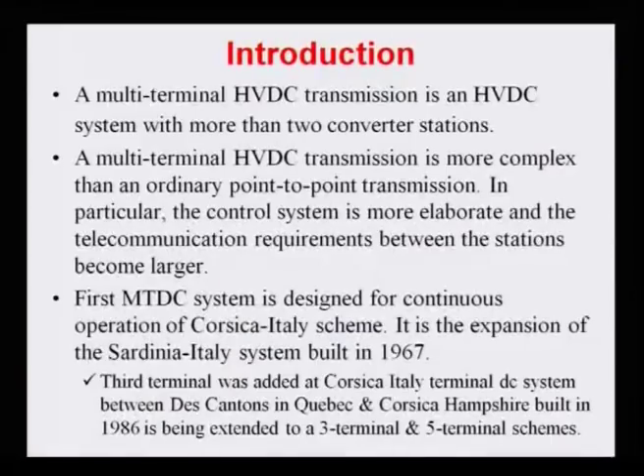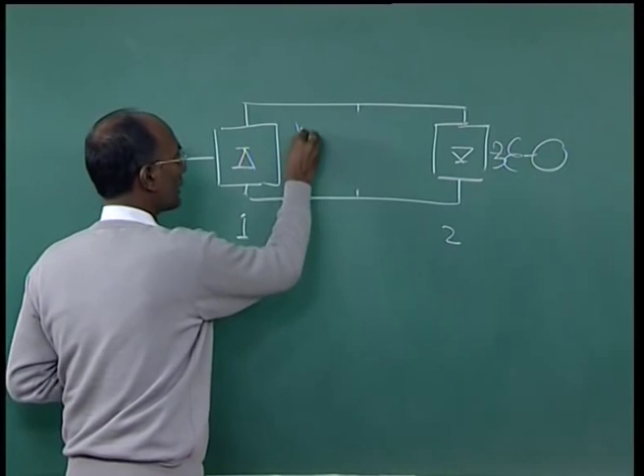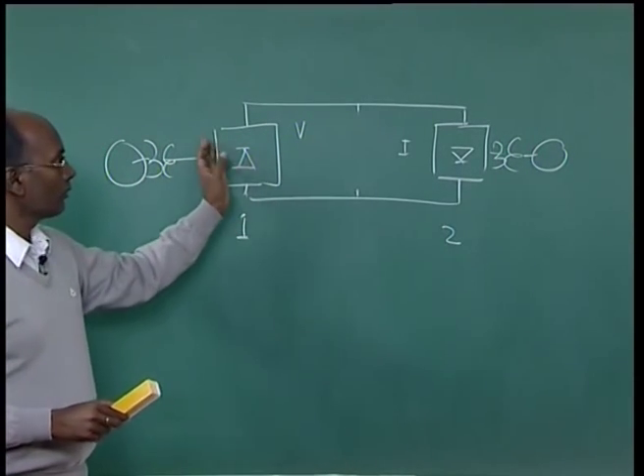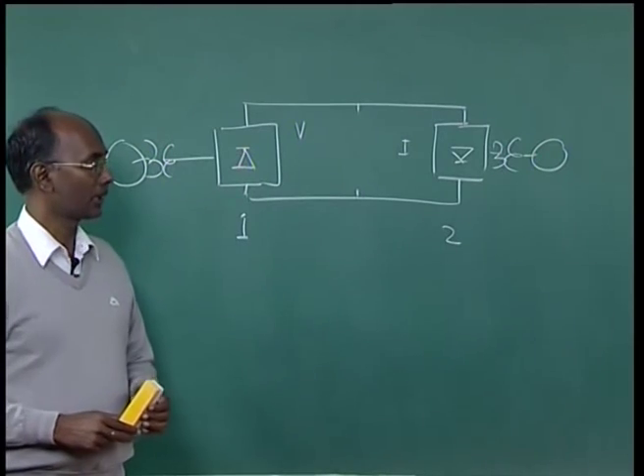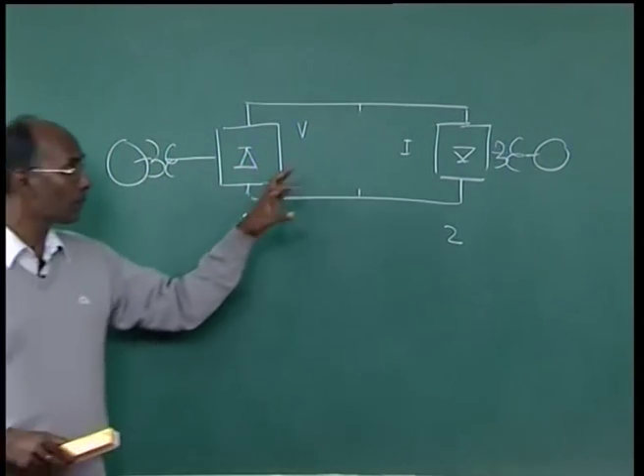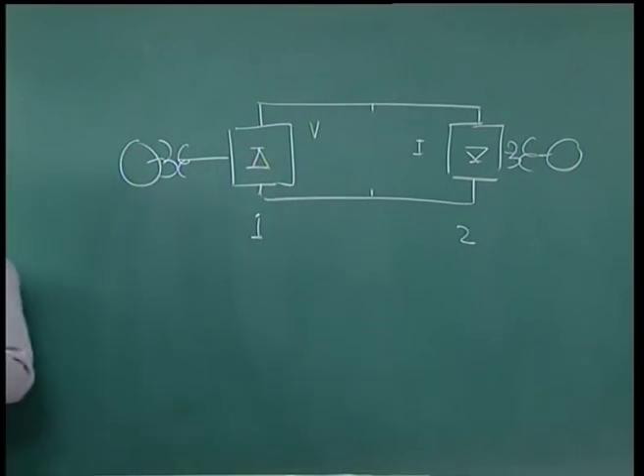The multi-terminal HVDC transmission system is more complex than the ordinary point-to-point or two-terminal HVDC system. In particular, the control system is more elaborate and the telecommunication requirements between stations become larger. In a two-terminal system, one terminal controls voltage and the other controls current, requiring a communication channel. With more terminals, we need more and more telecommunication between all converter stations.